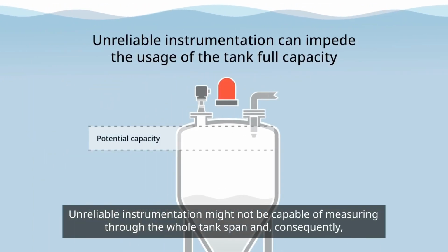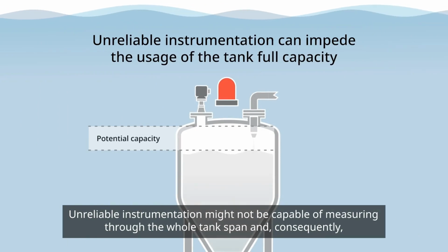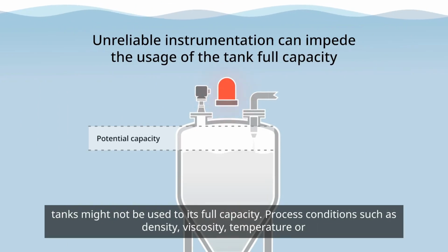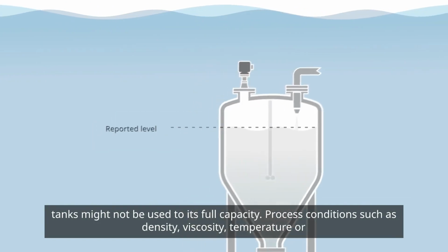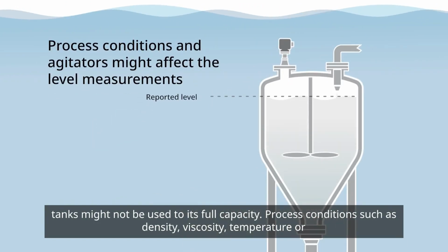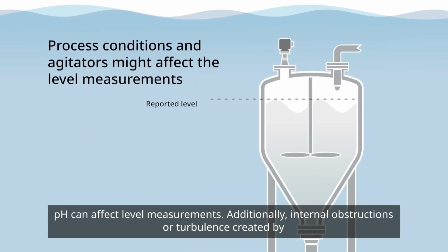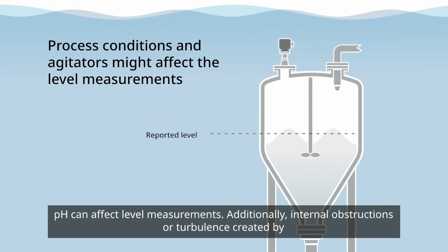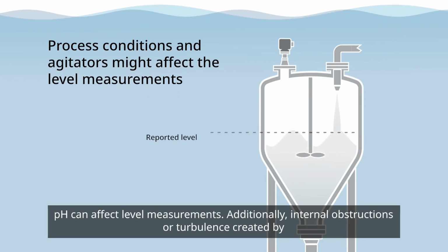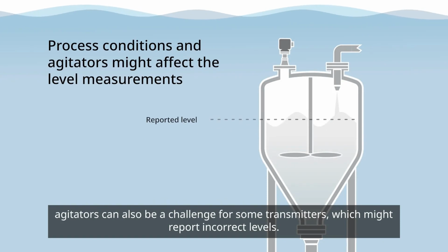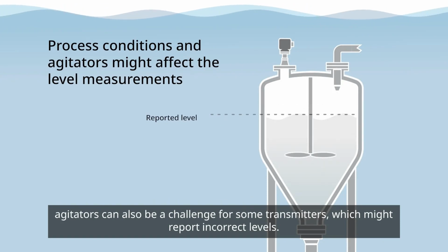Unreliable instrumentation might not be capable of measuring through the whole tank span, and consequently, tanks might not be used to their full capacity. Process conditions such as density, viscosity, temperature, or pH can affect level measurements. Additionally, internal obstructions or turbulence created by agitators can also be a challenge for some transmitters, which might report incorrect levels.